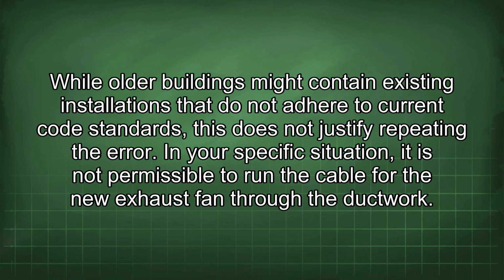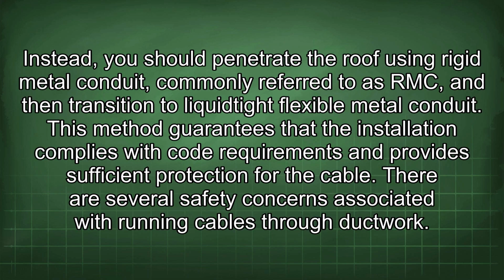the ductwork. Instead, you should penetrate the roof using rigid metal conduit, commonly referred to as RMC, and then transition to Liquidtite flexible metal conduit. This method guarantees that the installation complies with code requirements and provides sufficient protection for the cable.